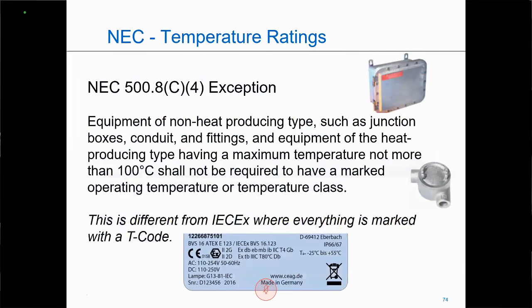Now, the code also has an exception that we see listed. This is a little different than the IEC world. In the IEC world, we're used to seeing temperature ratings marked on everything. But in our National Electrical Code, if the maximum temperature doesn't exceed 100 degrees C, we're not required to put a temperature rating on that particular product. You'll see this typically on junction boxes and fittings because they're not going to exceed 100 degrees C, so they won't have a temperature rating on those.